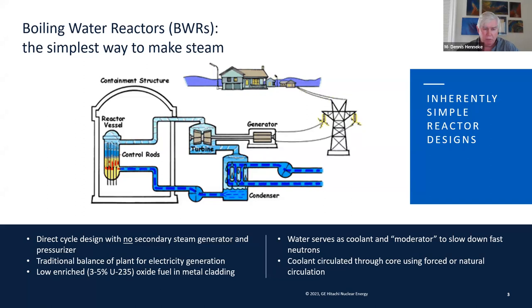I was a PWR PRA engineer for some 24 years, as well as did some startup work for Palo Verde and Shearon Harris. So I see pluses and minuses in both. The simpler design does help us in the area of SMR and advanced reactors. And of course, you have a slightly radioactive steam turbine generator, so you do have to shield that, and you have to worry about that during maintenance activities. But otherwise, the simpler design does allow us to get a plant that is lower risk and simpler than an advanced PWR.